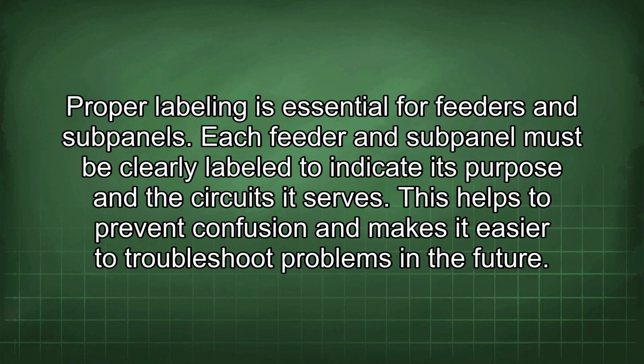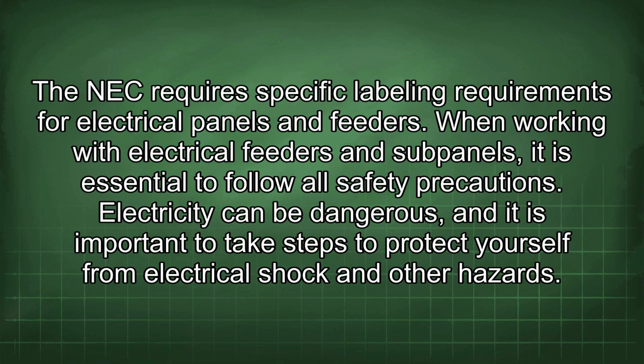It is also important to avoid running feeders through areas where they may be exposed to physical damage or corrosive substances. Proper labeling is essential for feeders and subpanels. Each feeder and subpanel must be clearly labeled to indicate its purpose and the circuits it serves. This helps to prevent confusion and makes it easier to troubleshoot problems in the future. The NEC requires specific labeling requirements for electrical panels and feeders.